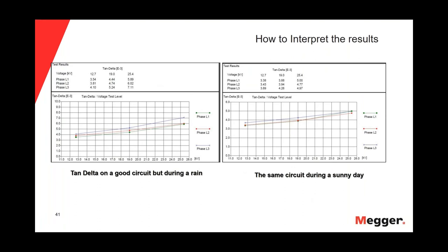The next slide shows how the weather can affect the results of the tan delta. The charts on the left show the tan delta results of a good cable measured during a rainy day — we can see higher tan delta measurements. On the right, the same circuit measured on a sunny day shows improved, lower tan delta values. So the weather can affect the measurements of the tan delta and is something we should consider.